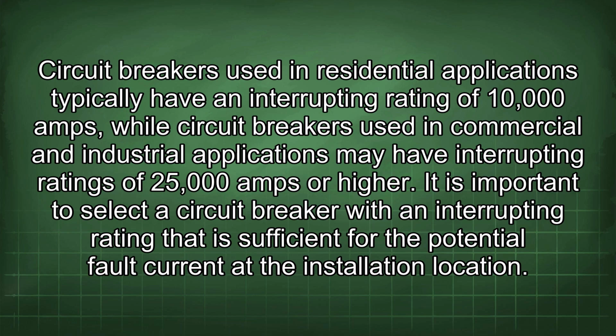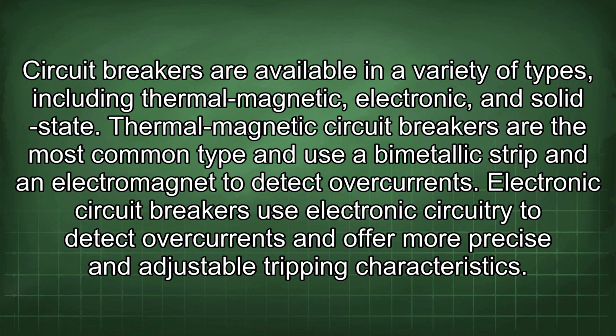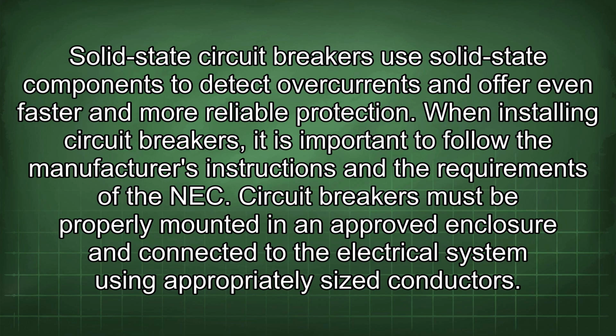at the installation location. Circuit breakers are available in a variety of types, including thermal-magnetic, electronic, and solid state. Thermal-magnetic circuit breakers are the most common type in use. They use a bimetallic strip and an electromagnet to detect overcurrents. Electronic circuit breakers use electronic circuitry to detect overcurrents and offer more precise and adjustable tripping characteristics. Solid-state circuit breakers use solid-state components to detect overcurrents and offer even faster and more reliable protection.